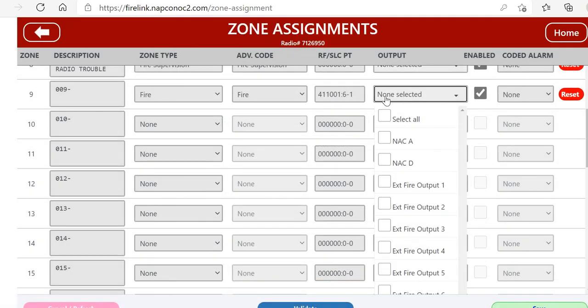Like we're programming zone 9, but if this is my first smoke detector, we can make it address one. The device point on this is going to be one. Then we can click okay and now the zone was programmed with the SLC point.